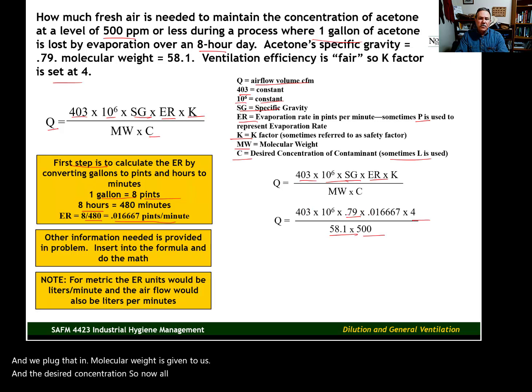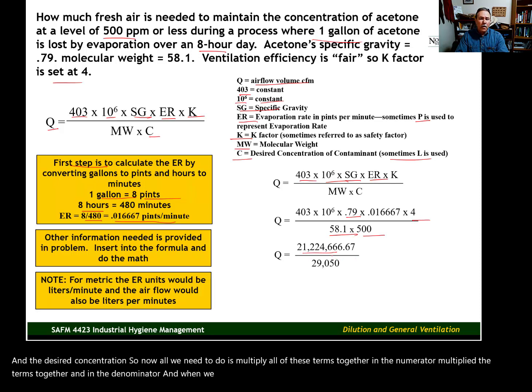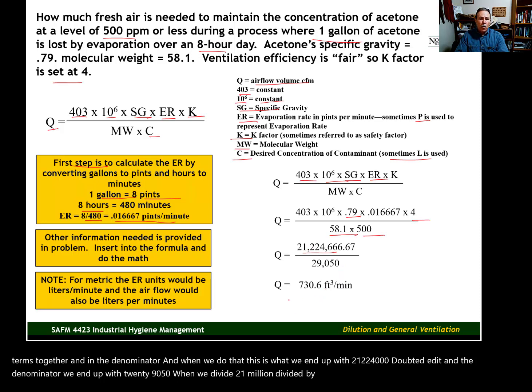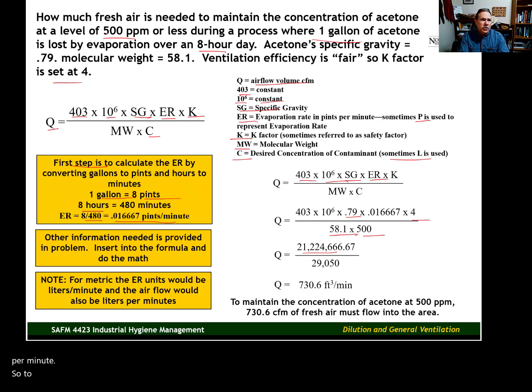So now all we need to do is multiply all of these terms together in the numerator, multiply the terms together in the denominator. And when we do that, this is what we end up with: 21,224,000 in the numerator. In the denominator, we end up with 29,050. When we divide 21 million divided by 29,050, we end up with a flow rate of 730.6 cubic feet per minute. So to maintain our concentration at 500 parts per million, we're going to need 730.6 cubic feet per minute of fresh air.